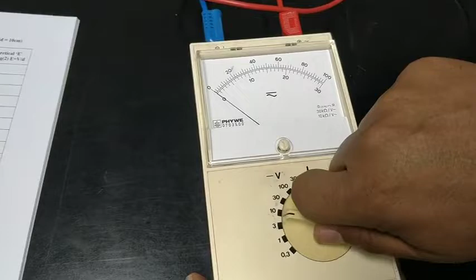Of course, I can change this if I want to. I can use the 3 or the 10 or the 30 or the 1, whichever I want. This does not change the measurements that you are doing. It will give you a better resolution if you want. So let's say if I am using the 3, it means I will be using the lower scale, and the maximum will be 3. So whatever is there, I will be dividing it by 10. So the 20 will be 2, the 10 will be 1, and the 30 will be 3. If I am using the 10, then I will be using the upper scale, and the maximum will be equal to 10. So this will be 10, this will be 8 and 6 and so on.